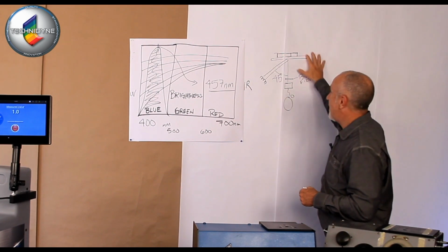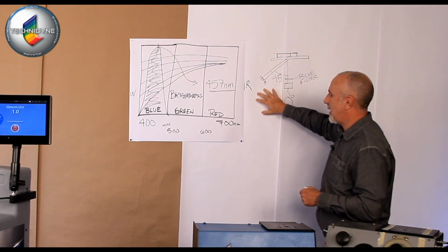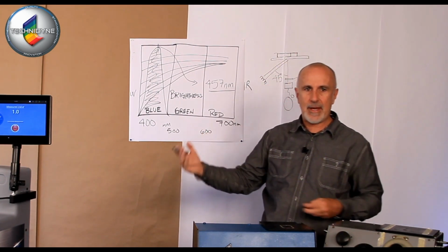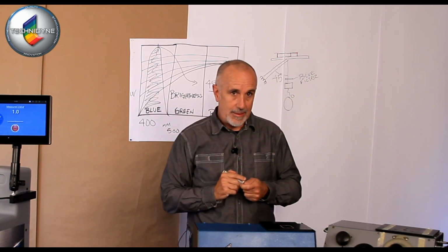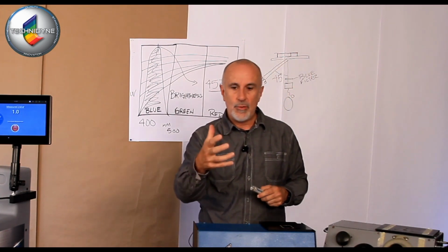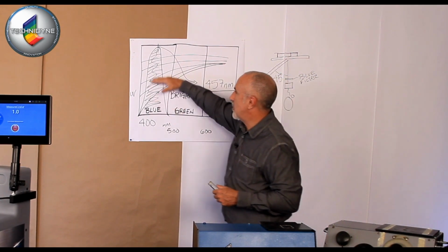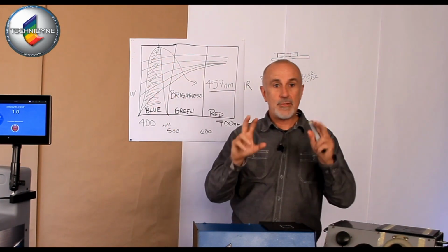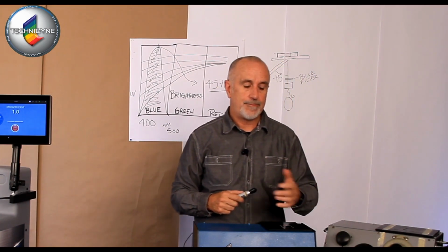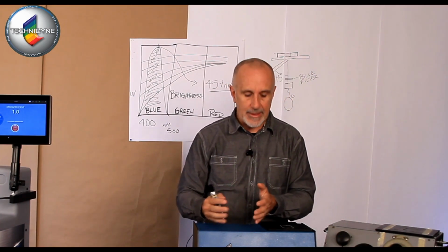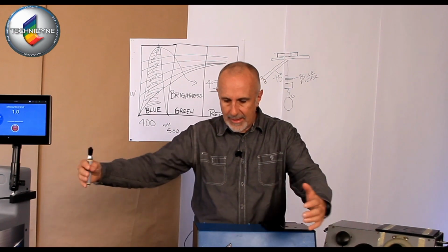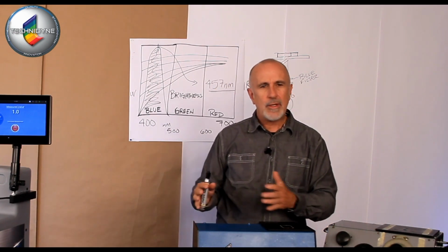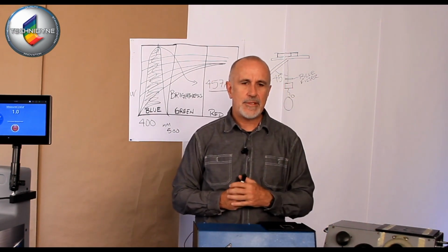Okay, that then was the instrument geometry that the Institute recommended to this manufacturer to simulate the viewing environment, to mimic and analyze the bleaching process, tying it together in a single function instrument that would measure this property they called brightness. Okay, so General Electric had provided them that spectrometer, but they weren't in the market of this kind of thing.